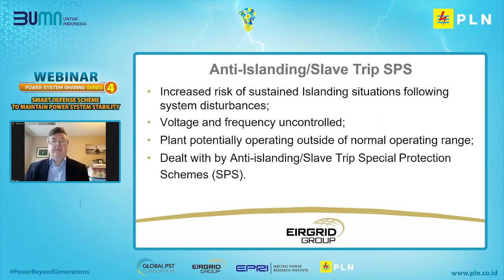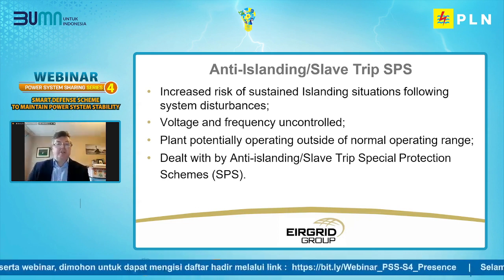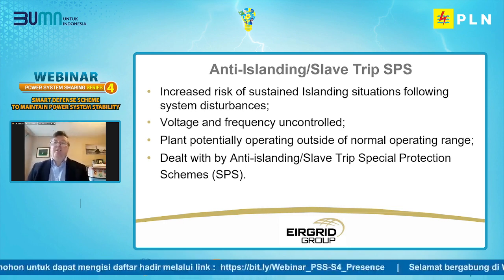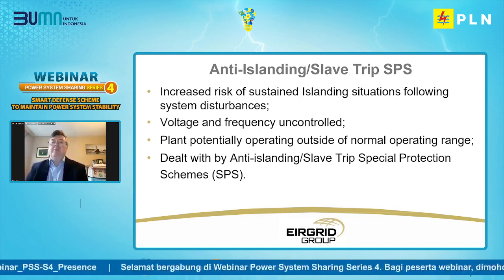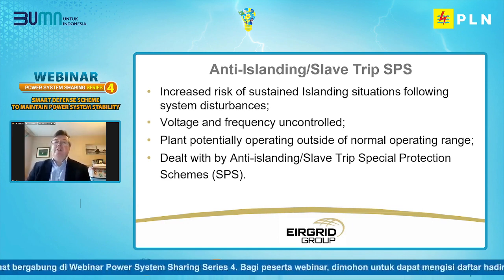With this arrangement, there's an increased risk of sustained islanding situations following system disturbances. Voltage and frequency can come out of control because parts of the network are no longer connected to the main system, and there's plant potentially operating outside normal operating ranges. This is dealt with by anti-islanding or slave trip special protection schemes. Next slide, please.